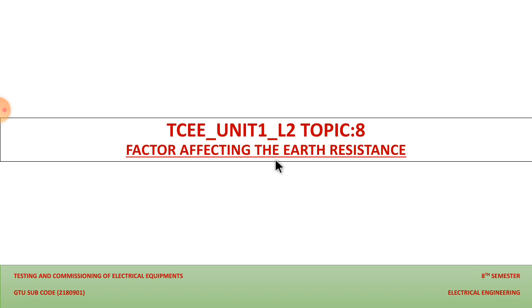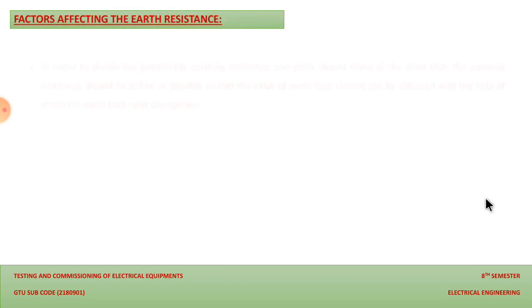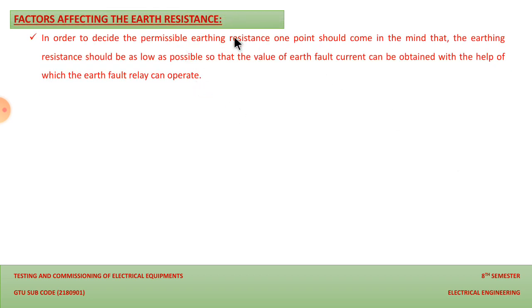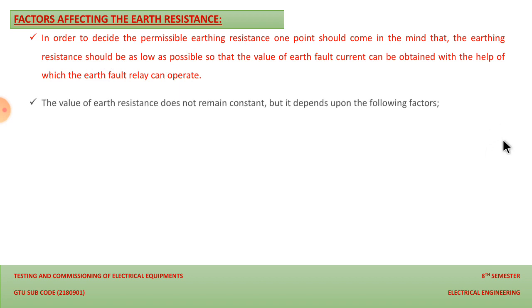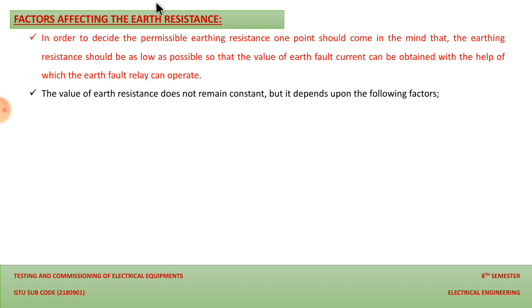So let us discuss topic number 8, factors which are affecting the earth resistance, that we should keep in mind while we are providing the earthing to any equipment or any system. In order to decide the permissible earthing resistance, one point should come to mind, that is earthing resistance, and we should keep it as minimum as possible for the better output. It should be as low as possible, so that the value of earth fault current can be obtained, with the help of which the earth fault relay can operate, that we already discussed. This is the main factor, that is earth resistance. So we should keep it as minimum as possible where we have placed our earth rod.